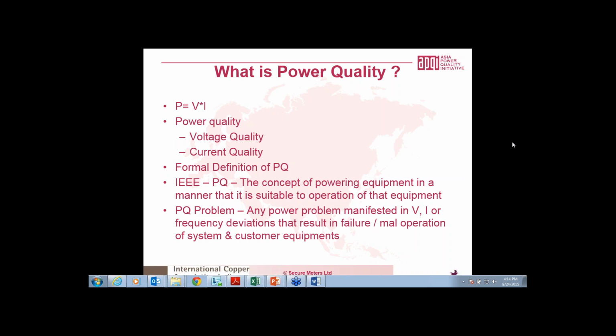There's a classic example which comes to my mind when we are talking about PQ problems, which is robotic spot welding in an automobile machine. If that welding machine is missing out on certain spots in the welding, it's very difficult to diagnose, in the absence of power quality measurement, whether this miss is related to the malfunction of the machine standalone or is caused by the simultaneous appearance of a power quality feature, which can be an interruption or dip or transients or whatever it is.